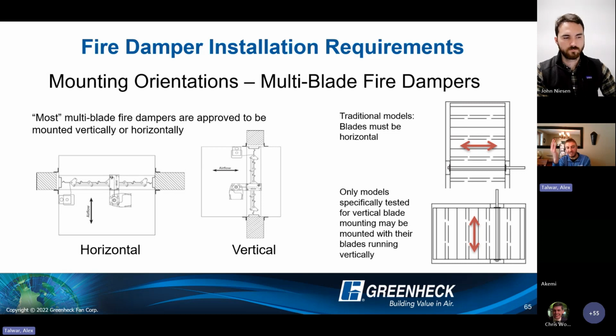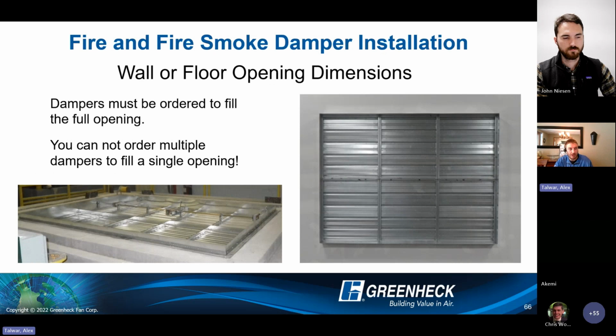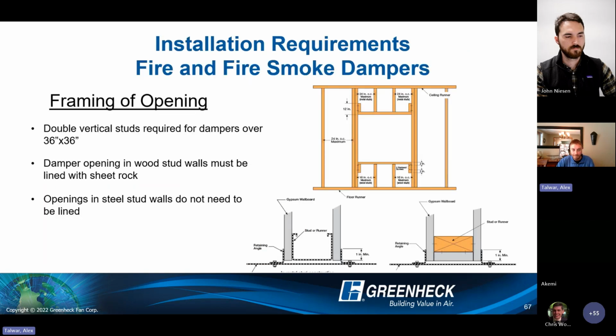Vertical blades, you usually only ever see that if someone wants actuator access at the top or bottom for some reason. But just know those are a specialized product. The dampers themselves, we've got to order them to fill the opening. This is certainly important. We can't bank a bunch of small damper sections together in the field to create one large damper. It's got to leave our factory in a UL approved manner and be ordered to fill the opening that it was intended for.